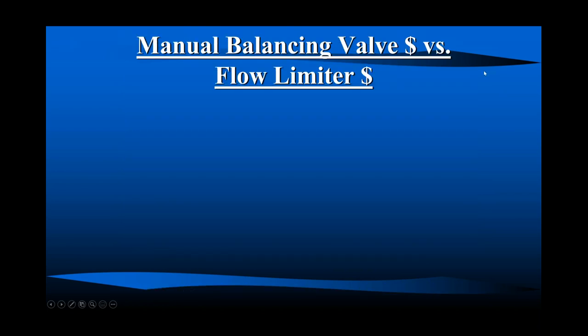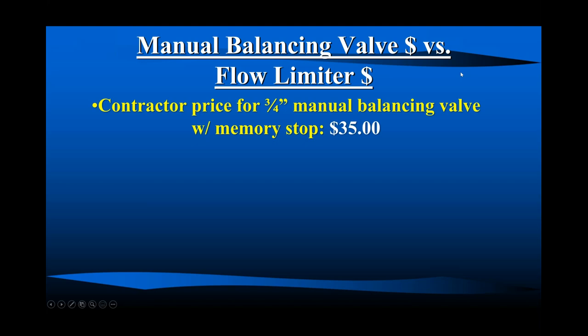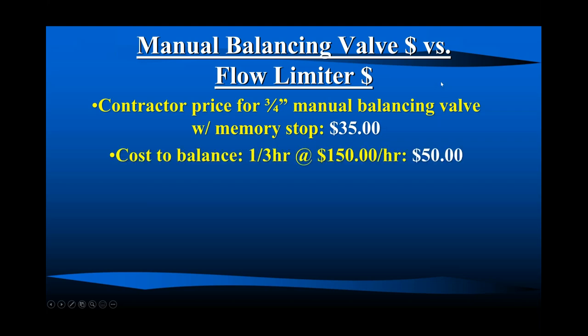Okay. So thank you for your attention so far without asking any questions regarding cost. So let's go through that. Manual balancing valve dollars versus flow limiter dollars. Contractor price for a 3/4 inch manual balancing valve with a memory stop, roughly $35. Cost to balance, if you do it right, you really have to touch it a couple of times, three times in most manual balancing valve manufacturers' installation manuals. Got to touch it three times, all of them. $150 an hour, 20 minutes, 7 minutes a touch, $50.